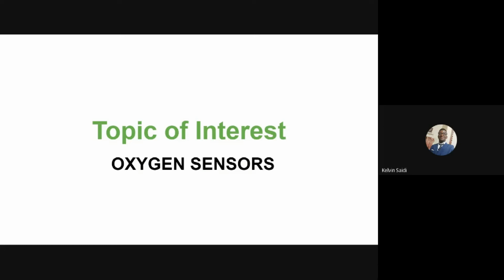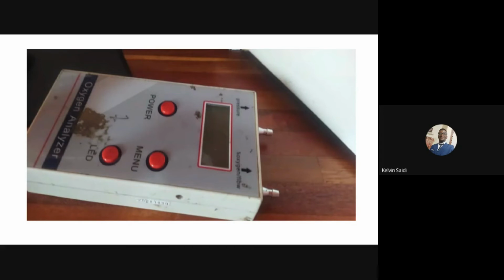Monitoring of this oxygen concentration is done by an electrical device called an oxygen sensor. This oxygen sensor measures the proportion of oxygen gas in a particular fluid. These sensors are usually either fitted inside the oxygen concentrators or built into handheld oxygen analyzers. So one can ask, why do we have oxygen sensors inside the concentrators while we also have oxygen analyzers? At times, the sensors in oxygen concentrators fail, and it can lead to false readings. So we need those oxygen analyzers. You can define an oxygen analyzer as a device that is used to measure the concentration of oxygen in a given environment. And in our case, the environment will be the oxygen that is coming out of the concentrator.